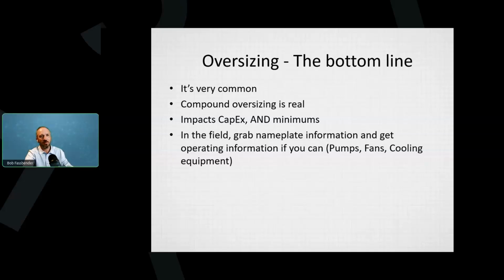So one thing with oversizing, we can basically assume most things are oversized. In the field, when you get the nameplate information and the equipment information, ideally you would find the actual operating information for pumps, fans, cooling equipment, etc. So if a pump is labeled 10 horsepower and there's a meter on it, you could find out, maybe you have to visit it twice, but just check out what the actual kilowatt draw is on it. And from there, you can get an idea of where that pump is running. Because if you pull the pump power and the fan power and you stick that into your model, it's probably not going to work out, assuming there's a variable speed drive on there. Same for cooling equipment. Most of it's oversized. If you can find out where it's operating, if there's building automation data, that's always really helpful.